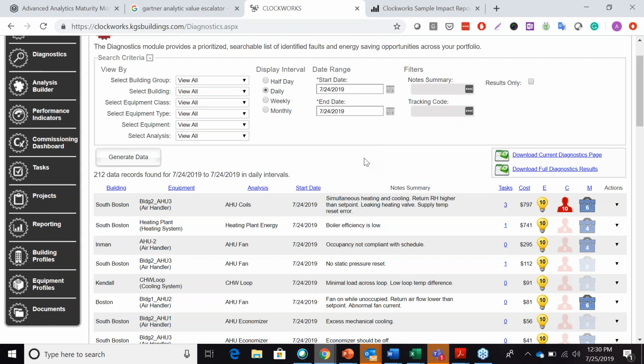So this is just a demonstration here. Again, 24 hours of the data, top priorities sorted by energy. So top one on the list here, I can see simultaneous heating and cooling. I can see return relative humidity is higher than its set point, that there's a leaking heating valve here, and a supply temperature reset error. In other words, there had been a reset program to drive efficiency, and that reset is in fact not being followed. So that points to the one-time, let's say, project or commissioning or optimization work versus a continuous approach.